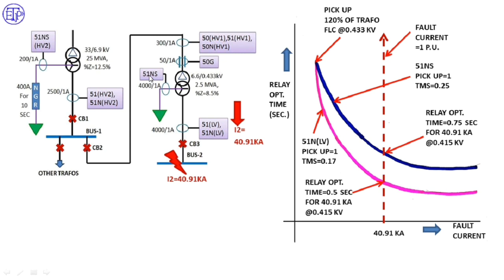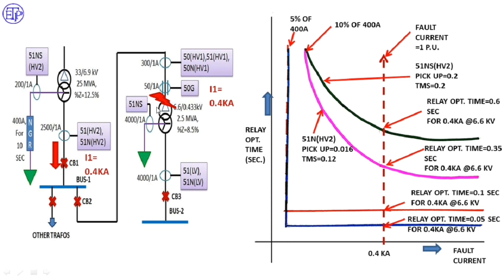Now let's look at the coordination graphs. For 51NLV and 51NS based on 40.91 kA fault current: since both relay pickups are set at 120% of transformer full load current, both curves start at the same point. The relay operating time of 51NLV is 0.5 seconds and 51NS is 0.75 seconds — you can see the time gradation. The coordination ensures that if there is a fault at Bus 2, 51NLV operates first, and if it fails, 51NS operates as backup.